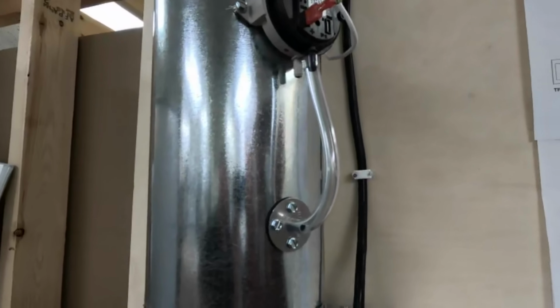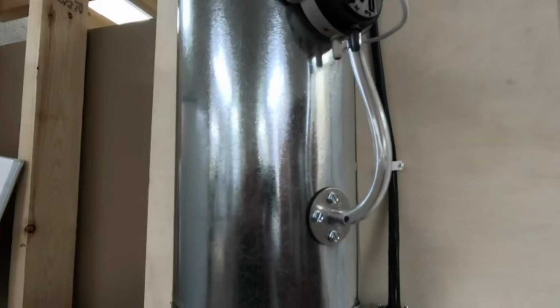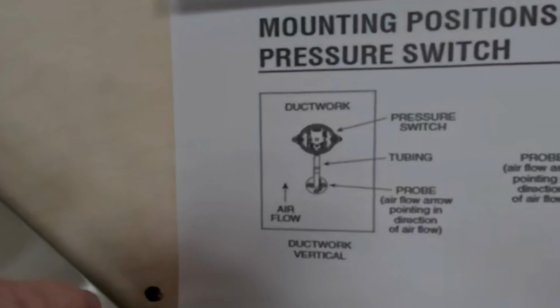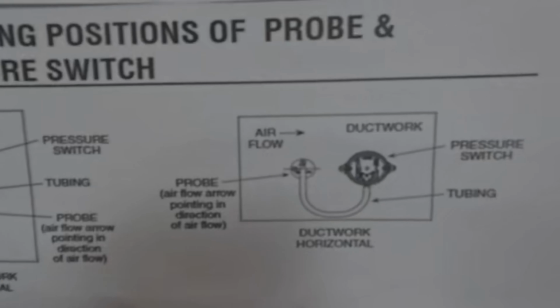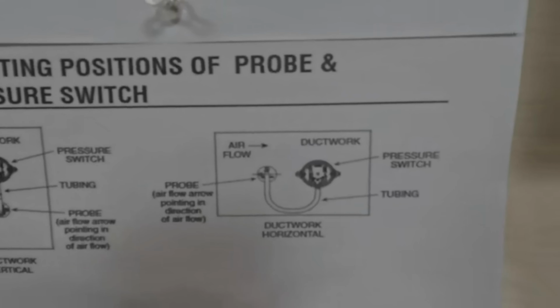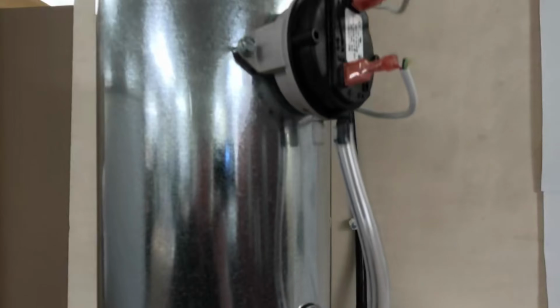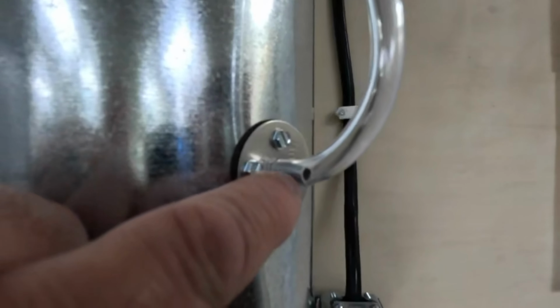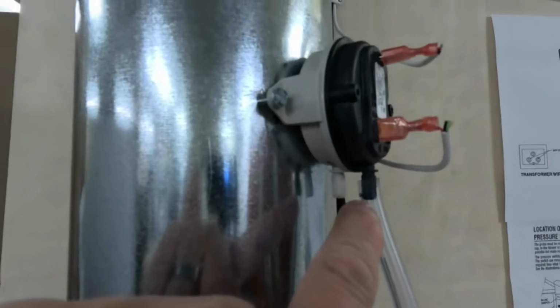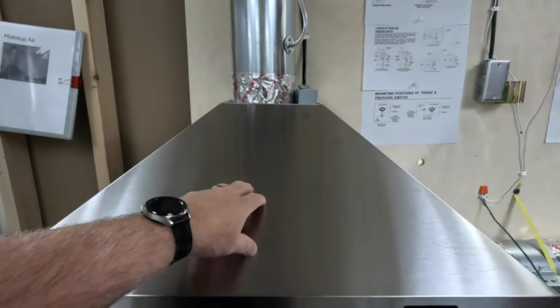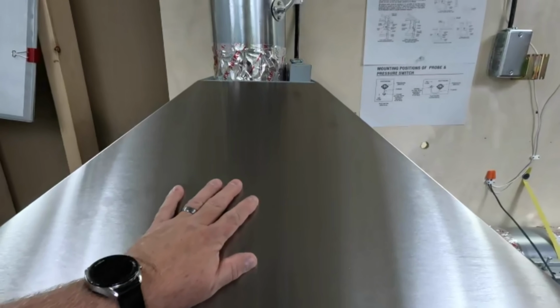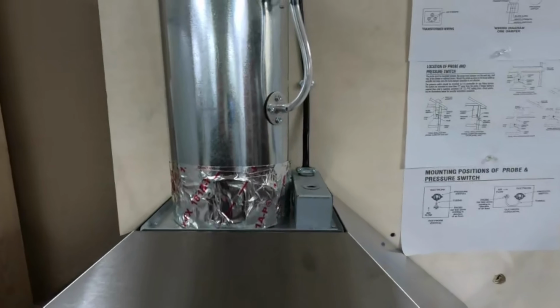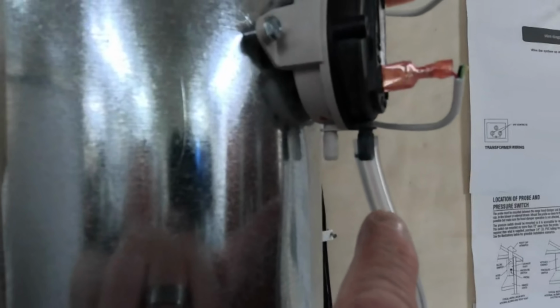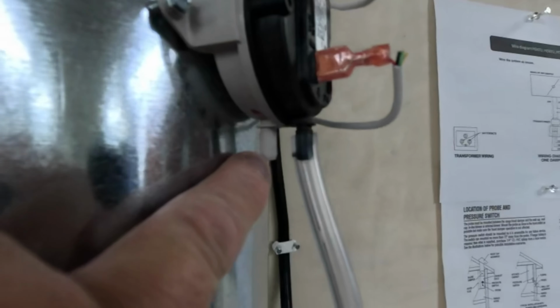We have great instructions on our website, and a manual comes with the unit. Here you can see this is for vertical ducting, and this is horizontal ducting. The main thing to remember when you do this is when you hook the pressure switch up. Right now I have it set for internal blower system. That means the motor is mounted inside the range hood. If I were using an inline or exterior blower, I would move this tube to this inner port right here, and that's the port you want to use, again, using an inline or exterior blower.